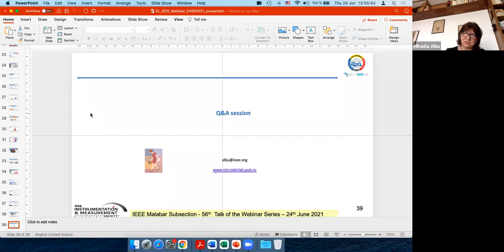We are still in the measurement area. Measurement means that the measurement equipment has to provide two values: one is the value of the measurand, let's say 230.4 volts, and the second, mandatory, is the standard uncertainty associated with that measurement, or the limits of error, a kind of explanation of the highest limit of error. After that, any algorithm for controlling or monitoring has to take into account these two numbers.